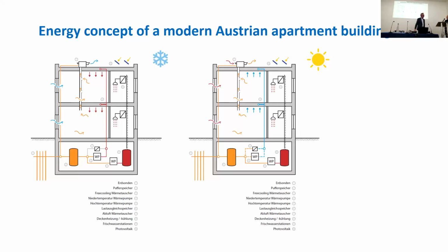Peter, can I ask you, do you run this through a sort of future climate screen? So do you test it against, say, 40 degrees centigrade outside or whatever you think might happen? Yes, we did, and it's robust. The recharging necessity will go down. So for the next 30 years, I feel safe that it's still more heating than cooling in our area. So this is robust. At the end, maybe we will have to release some of the cooling to the air if it shifts. This is why we always have an air heat exchanger added.